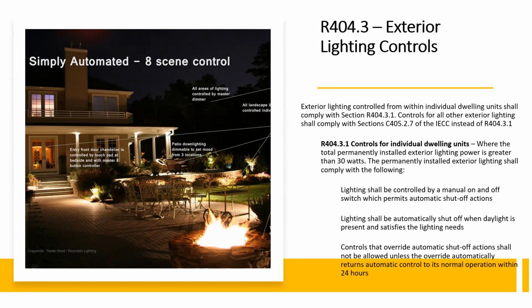So that's controls for individual dwelling units where the total permanently installed exterior lighting is greater than 30 watts, then the permanently installed exterior lighting shall follow these below. Lighting shall be controlled by a manual off and on switch that permits automatic shutoff actions. In other words, it can be switched off and on, but it needs to revert back to automatic shutoff. Lighting shall be automatically shut off when daylight is present and satisfies lighting needs.